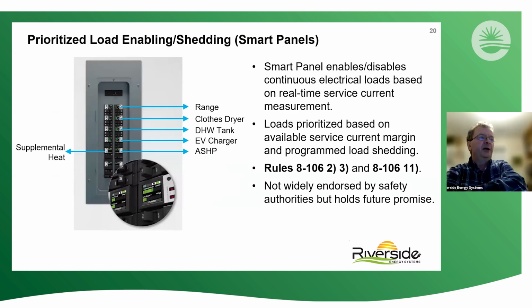What is emerging as another promising technology, and it's being used extensively in Europe and Asia and even parts of the US now, is using smart panels that not only can measure the total demand on the service, but also can measure the demand from individual loads like an electric range, a clothes dryer, EV charger, air source heat pump, etc. And through priority programming, selectively shed loads in real time to make sure that we never exceed the service demand. This technology is tried and proven, and it's emerging and gaining traction all over the world.